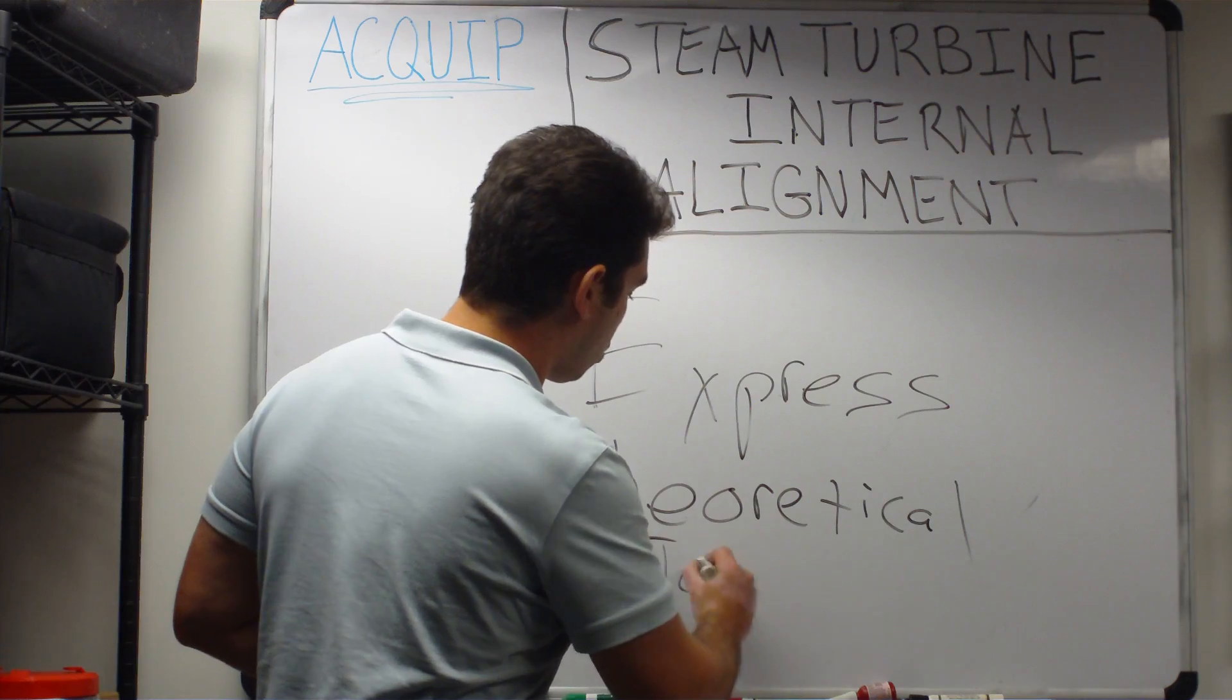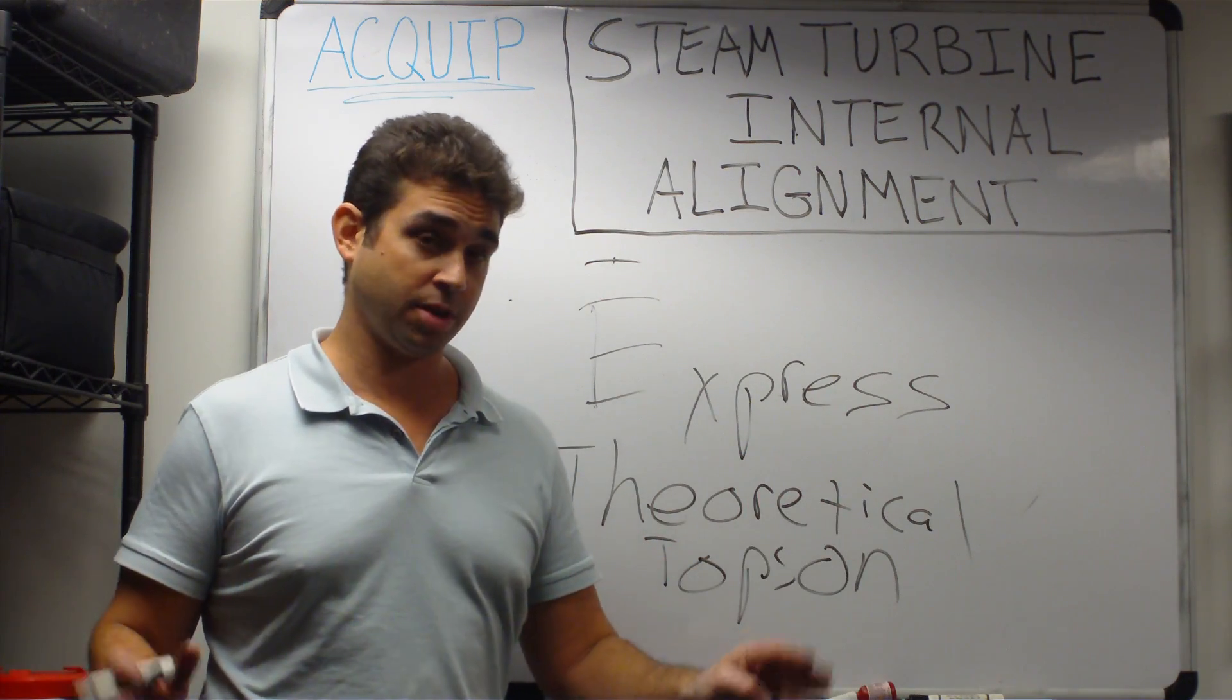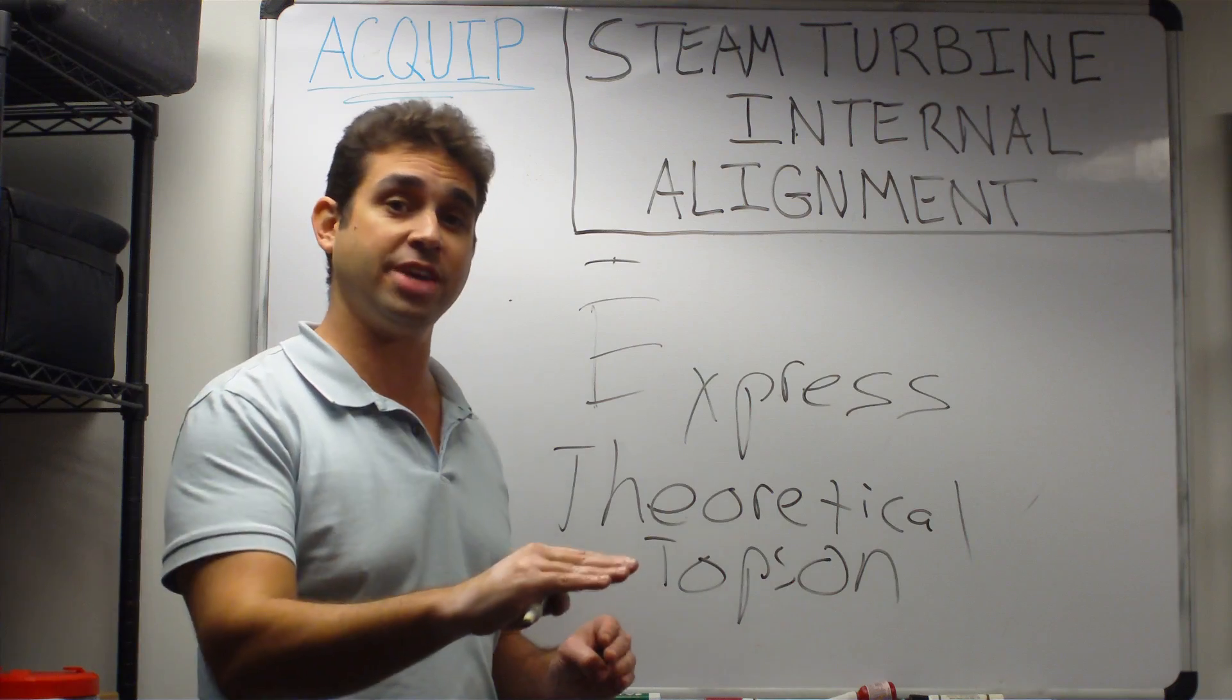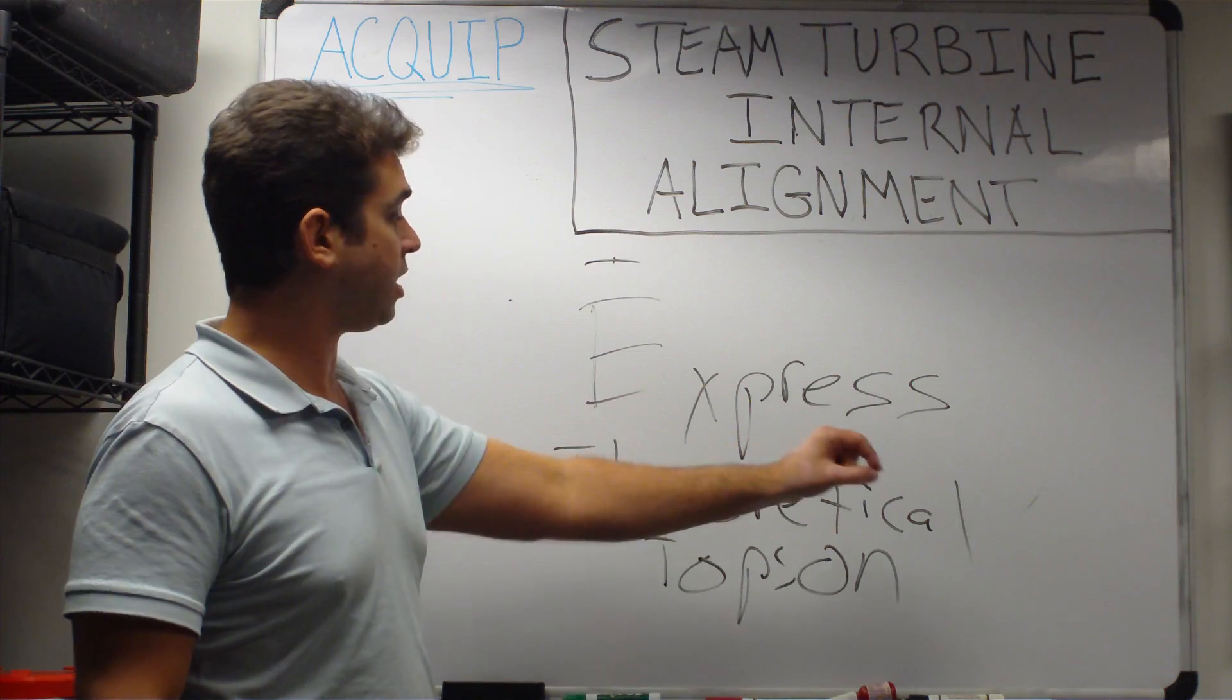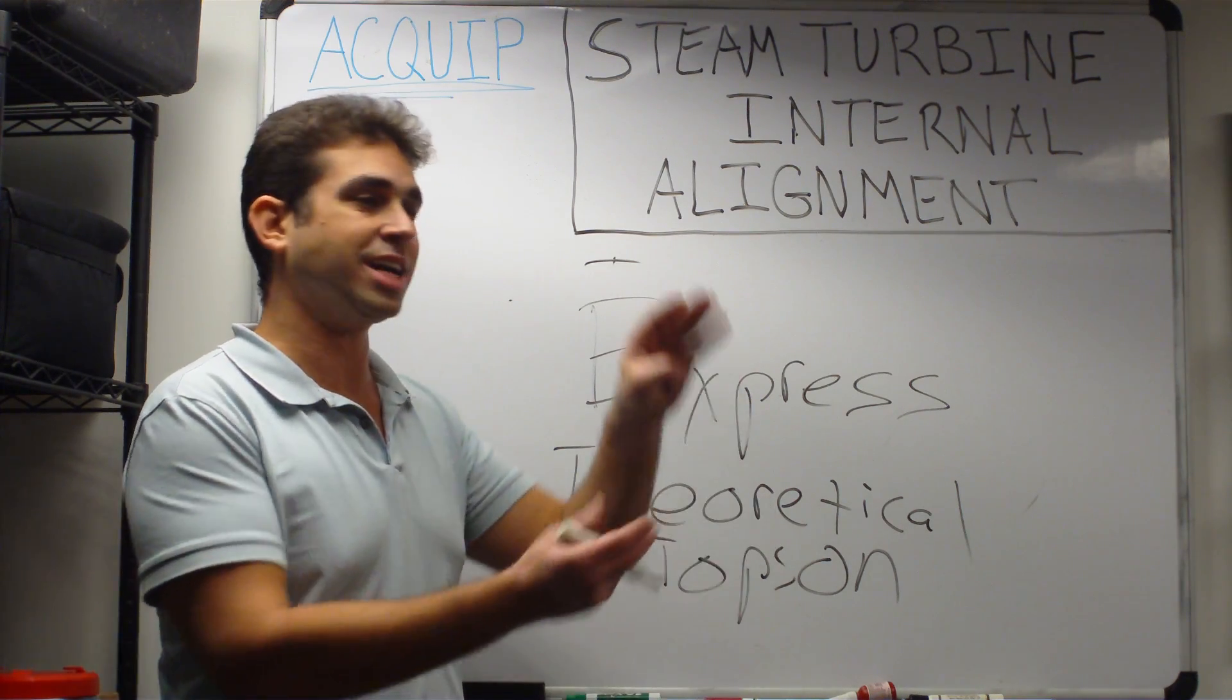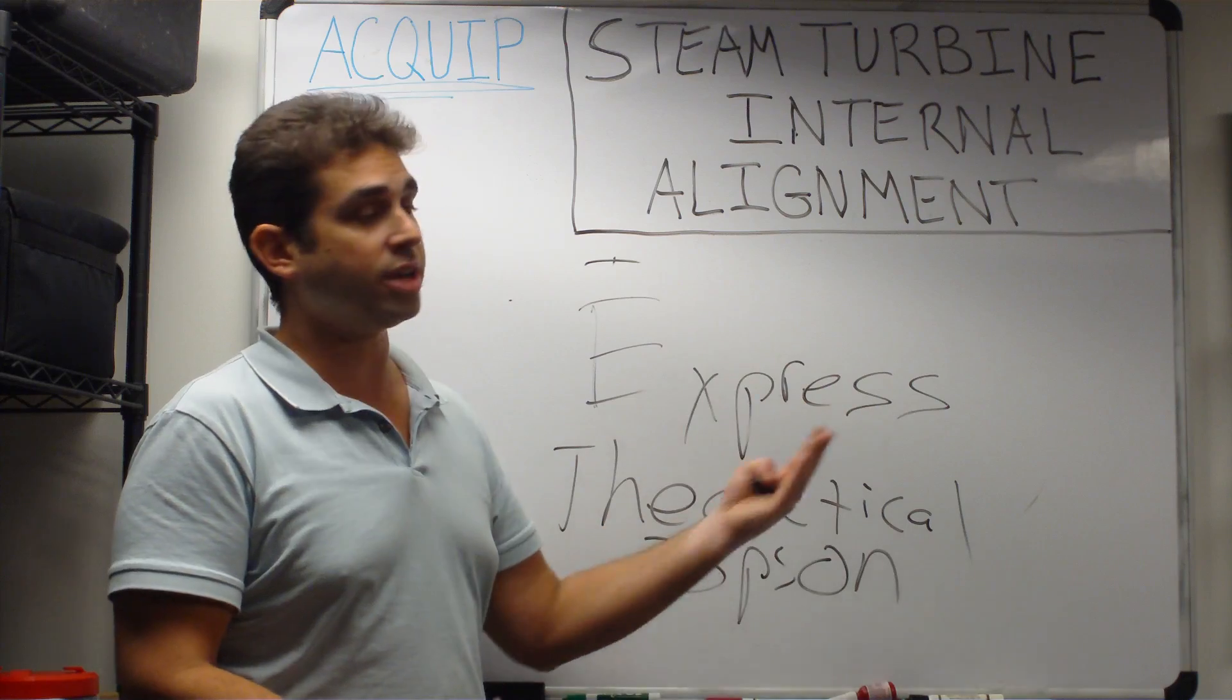because what we're going to do in this type of alignment is only take tops off readings, but we're going to calculate the out of roundness, we're going to calculate the horizontal joint deviation, we're going to take actual rub measurements on any of the diaphragms, and any of the packing that's in, and any of the seal strips, and we're going to calculate where the turbine was running with the top on without actually putting the top on.